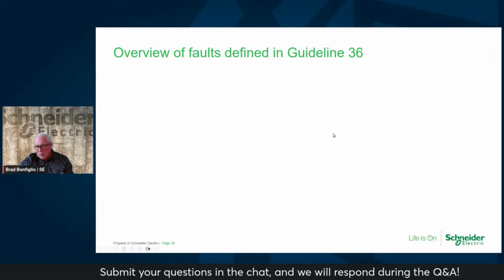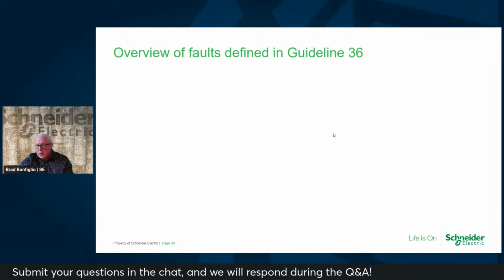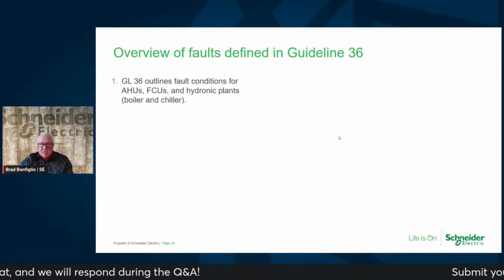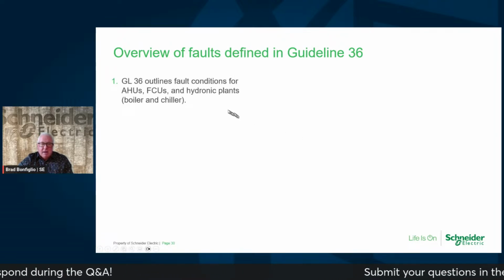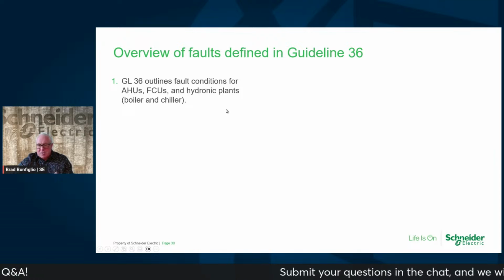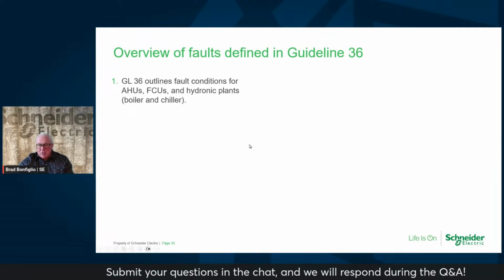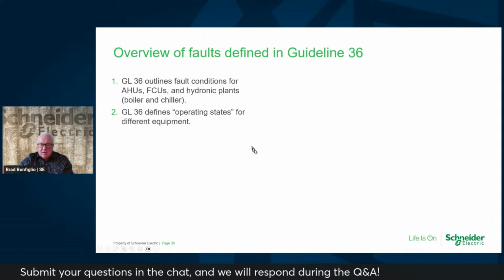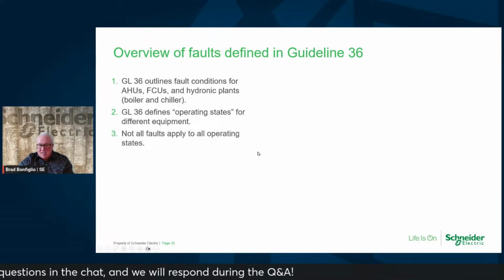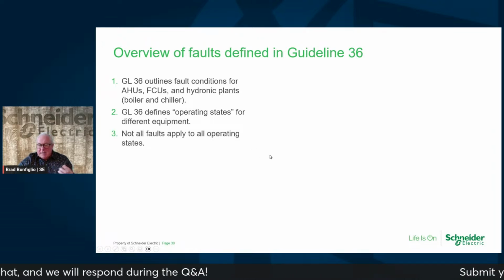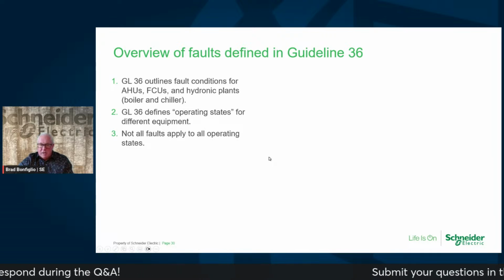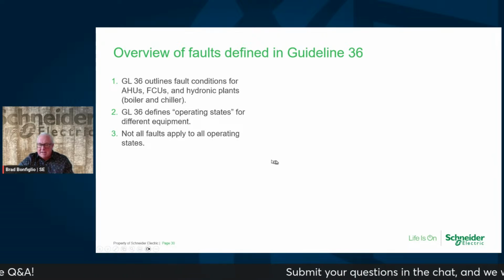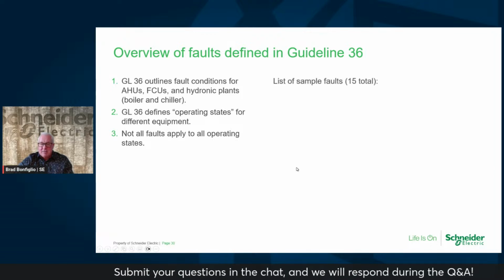ASHRAE 90.1, if you look through it, is really around the air handler faults. This gets into a little more granular into other faults. So let's take a look at this. They outline the different faults, and again, we're trying to do this for the different systems as they become available. It talks about the different operating states. They don't apply, and these are in addition to your alarming, right? This is in addition to something actually breaking, to find out what's really happening as a root cause analysis.